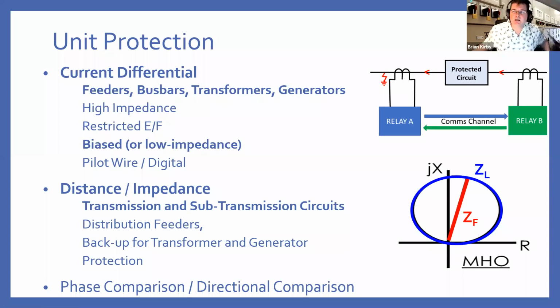Distance and impedance protection works on the principle that if you can work out the impedance on your circuit, you can determine whether the system is healthy or there's a fault in your zone of interest. This diagram shows what's called a mho, which is an ohm in reverse. If you remember, I mentioned the UK power system is generally at about 70 degrees lag. So this is your reactive power, and you're about 70 degrees there. If you've got a fault, it's going to be somewhere on that red line. You would expect it to initiate there. It may move after the fault's established, but initially your fault will start somewhere along that line.